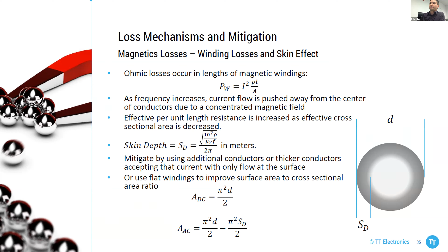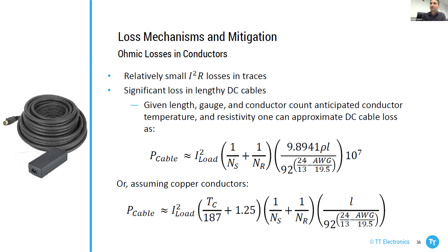In external power conversion, offline converters, one of the main loss mechanisms is simple conduction losses inside traces on the secondary side of the converter and inside DC cables. If we've got a long DC cable with thin gauge, we're getting a ton of losses there. That's one of the most dominant mechanisms at higher load conditions, and this is related to the square of the load.